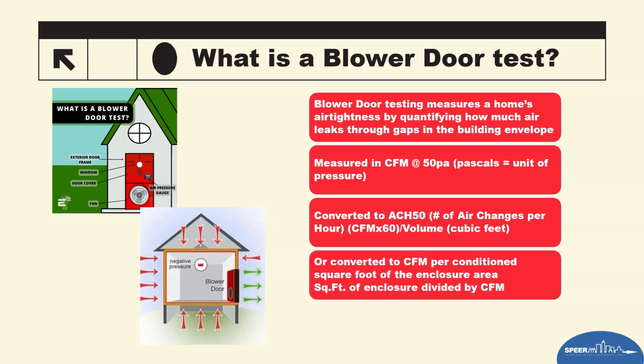In the 2021 code, there are now two ways to do it. In the 2018 and prior, there's only one way, and that's ACH. 2021, 2024, going forward, there are two ways. ACH is the first and foremost. It's air changes per hour. It's calculated by taking the CFM, multiplying it by 60 to convert to an hourly rate, and then dividing by the conditioned volume. For foam encapsulated houses, that includes the entire volume of the attic. Once you divide the volume into that hourly rate, you get air changes per hour.